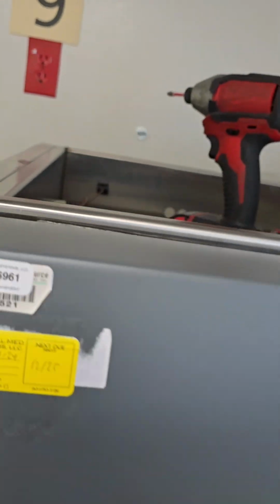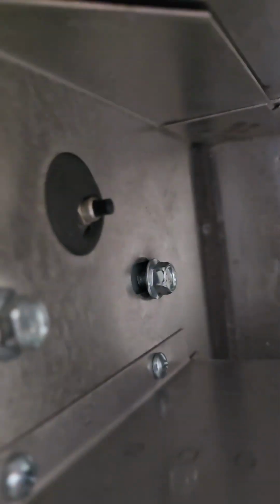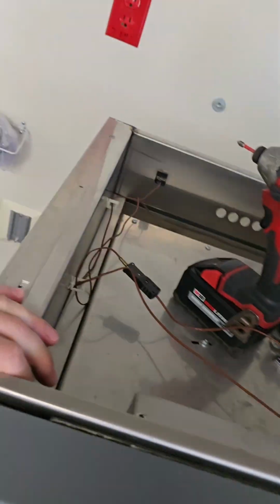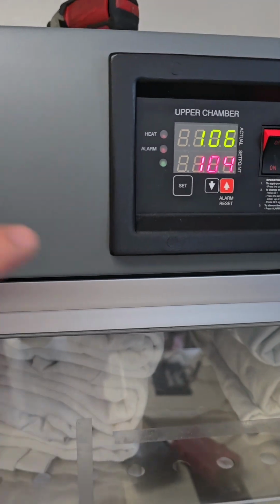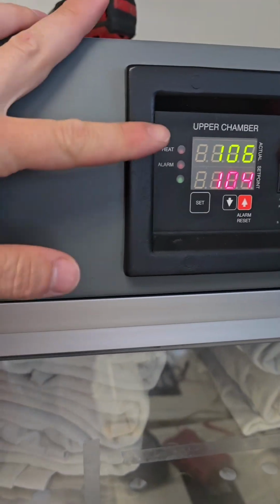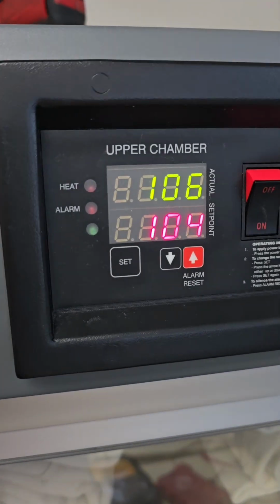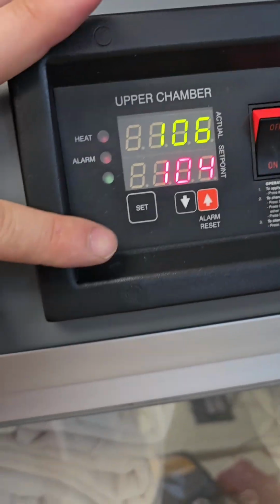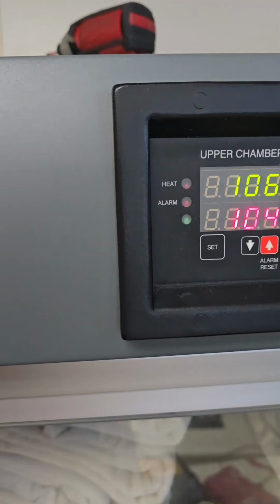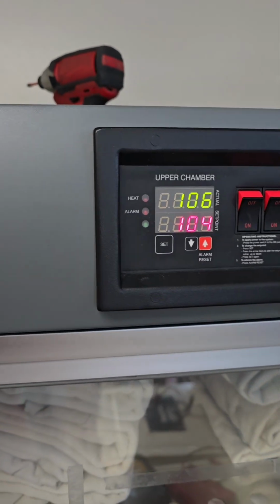Then you have to remove the top. Inside you'll find a calibration button. See that black guy right there? This guy next to the nuts in the top cabinet. While you're pressing that, you have to hold down the set and up arrow for about 3 seconds until your display changes to a J1C or INT. Then you can let go of set and up. Continue holding the button in the back. You have to hold this the entire time until everything's finished.